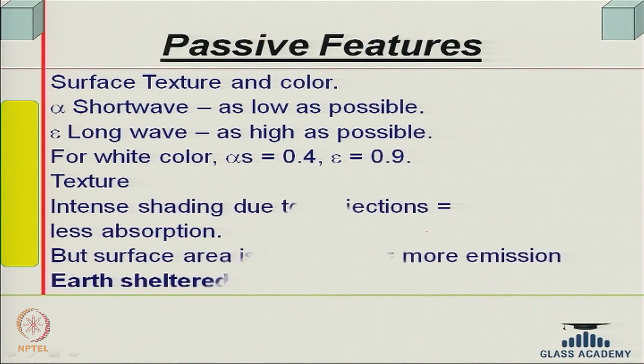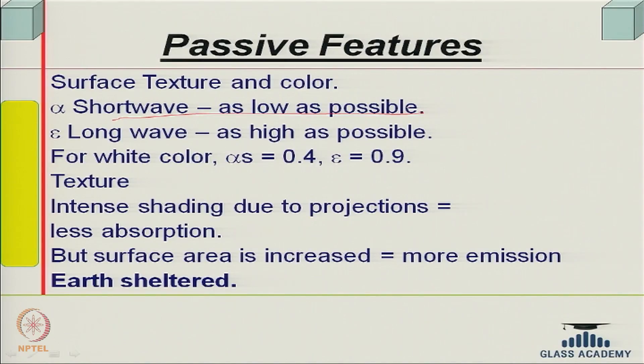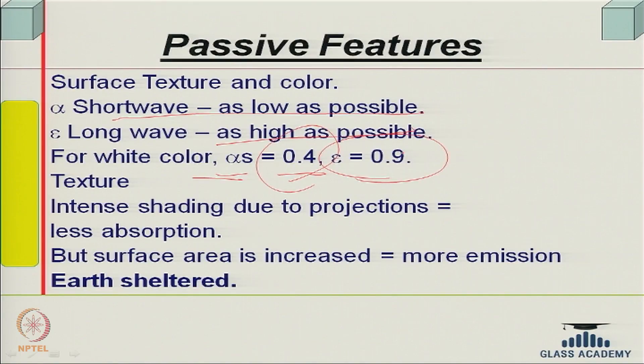Surface texture and color are very important. Short wave absorptivity should be as low as possible — the wall should absorb minimal radiation — but long wave emissivity should be as high as possible so that at night it radiates as much as possible. For a white surface, alpha equals 0.4, meaning short wave absorptivity is 40 percent, but its long wave emissivity is 0.9, so it emits out most of the heat.